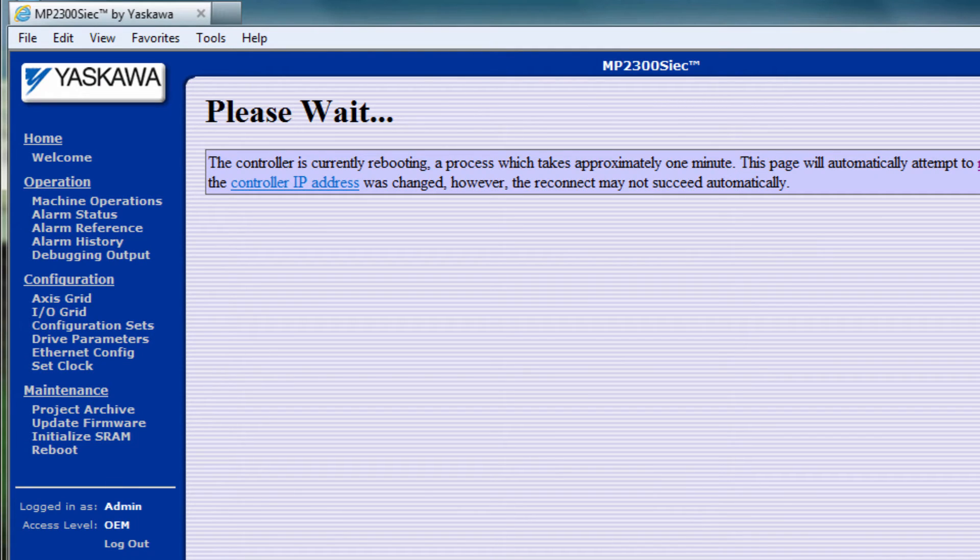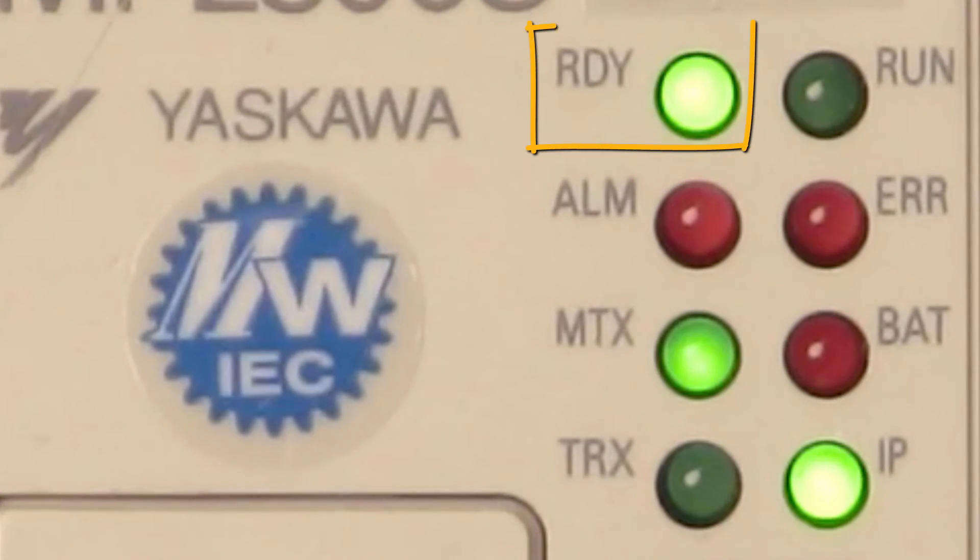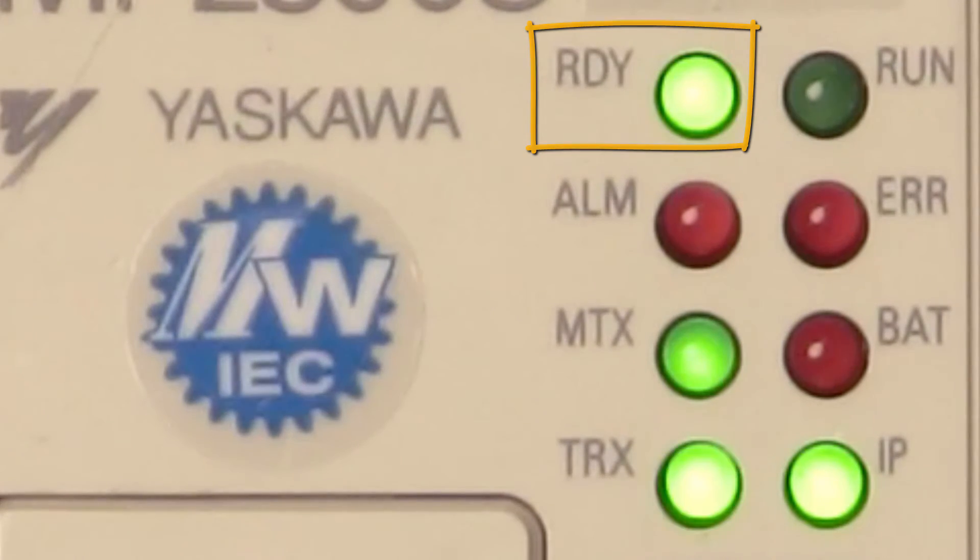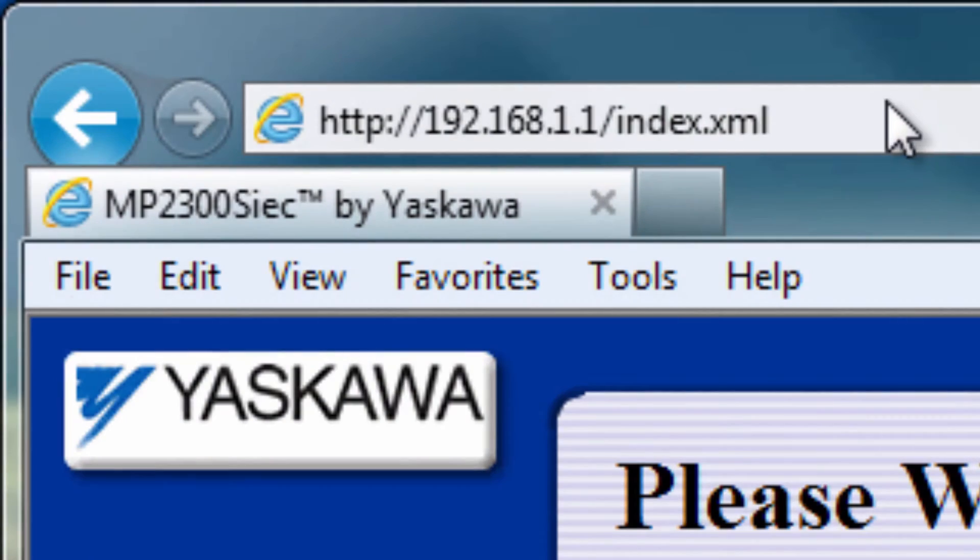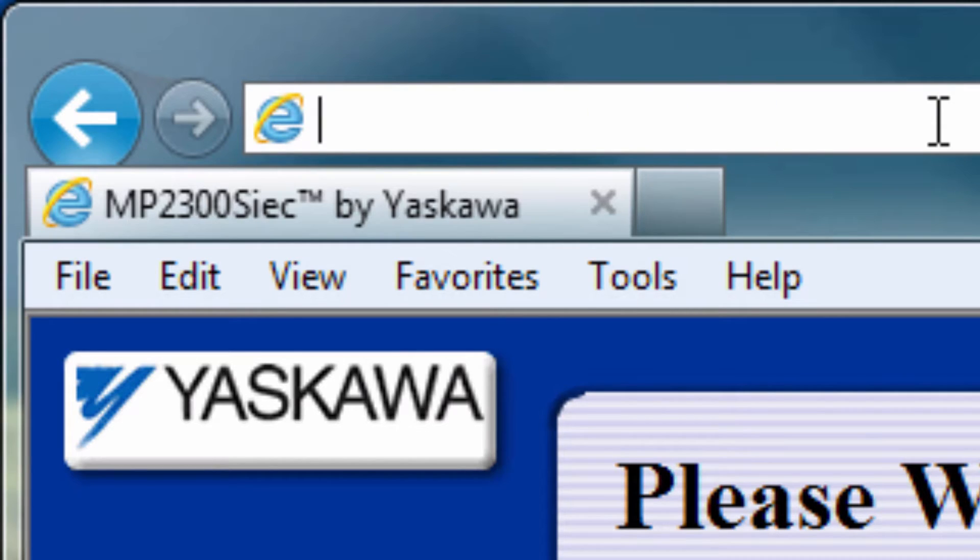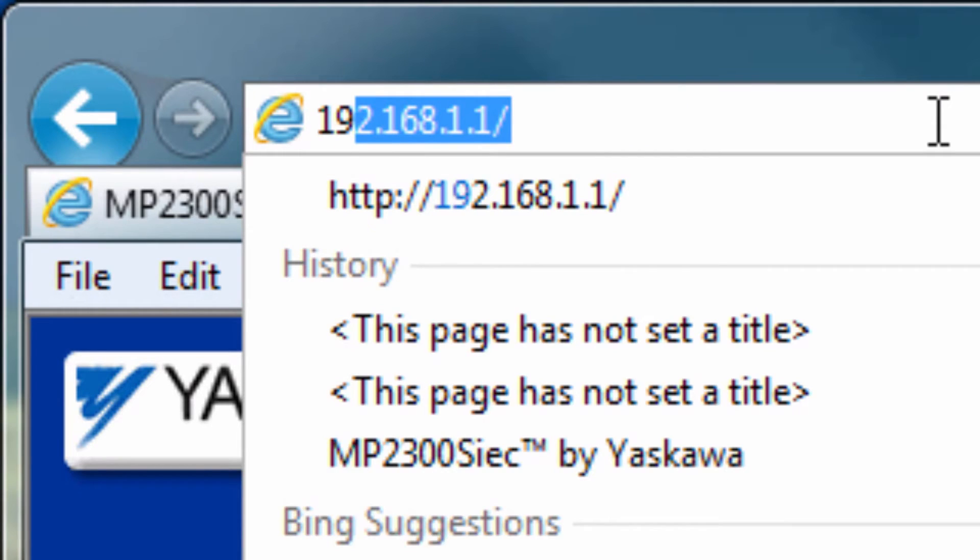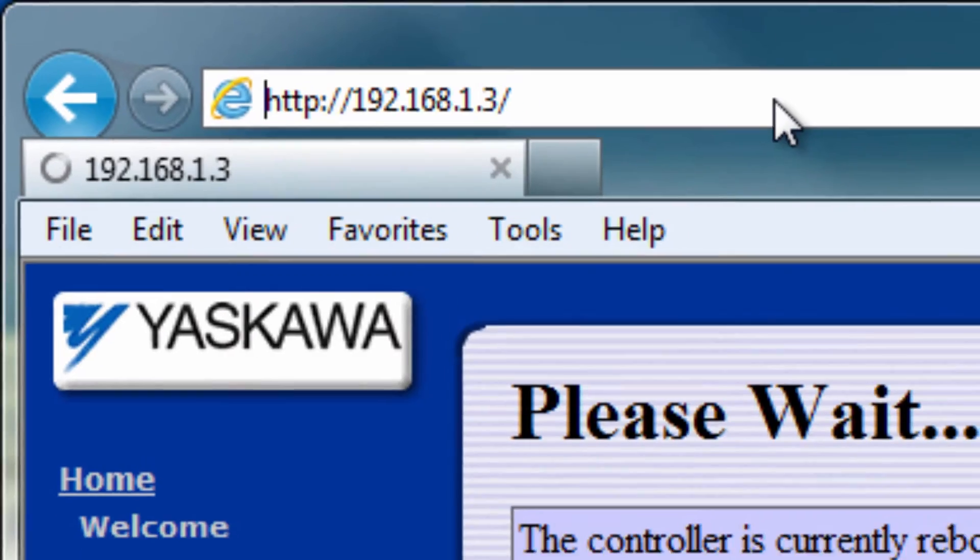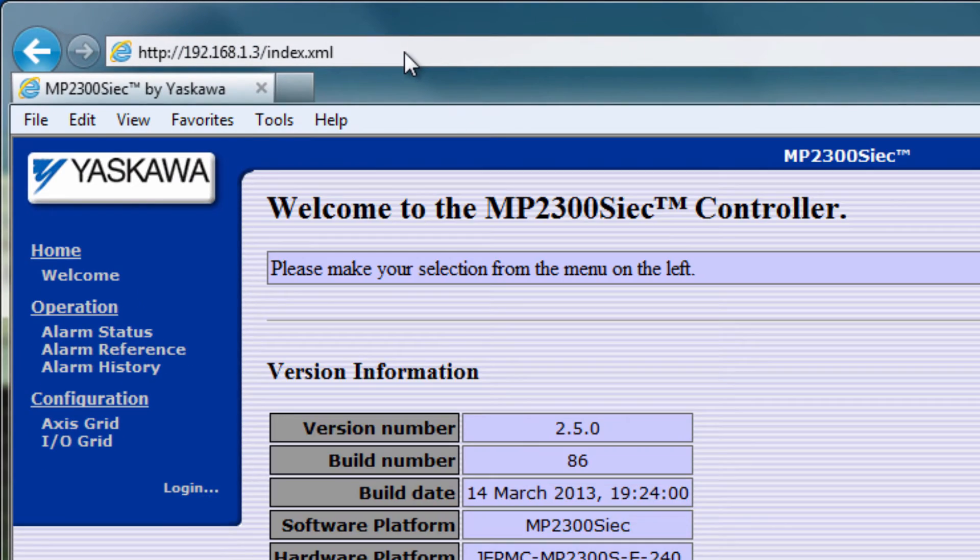If applicable, reconnect the controller to the network and adjust the PC's IP address to be compatible with that of the controller. When the ready light turns on after reboot, enter the configured IP address in Internet Explorer 192.168.1.3 in this case. The controller IP address has been found and connection confirmed.